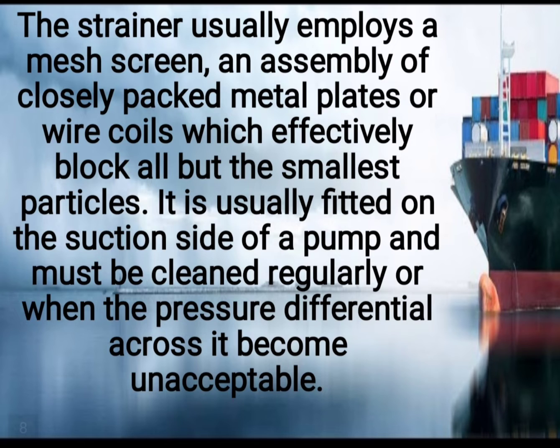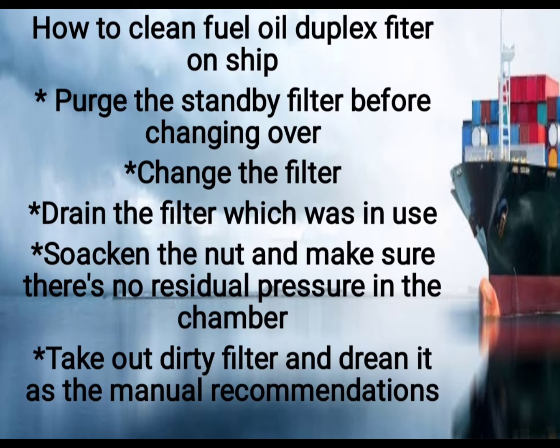It is usually fitted on the suction side of a pump and must be cleaned regularly or when the pressure differential across it becomes unacceptable. And next is how to clean or maintain the fuel filter. First, purge the standby filter before changing over. Second, change over the filter. Third, drain the filter which was in use. Fourth, slacken the nut and make sure there's no residual pressure in the chamber. Fifth, take out the dirty filter and clean it as per the manual recommended actions.